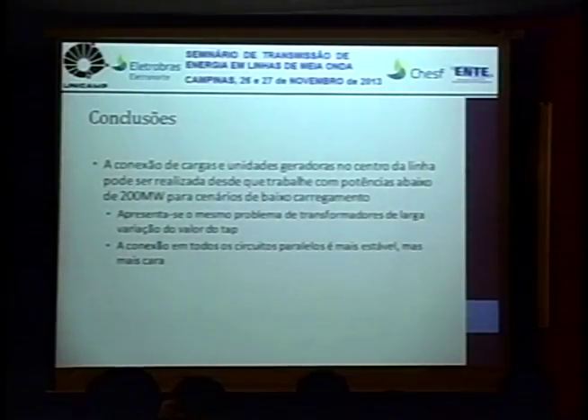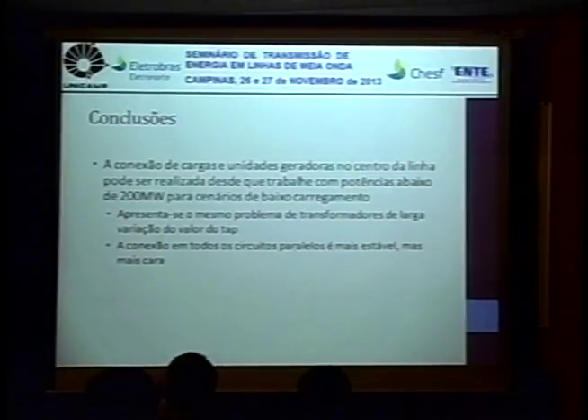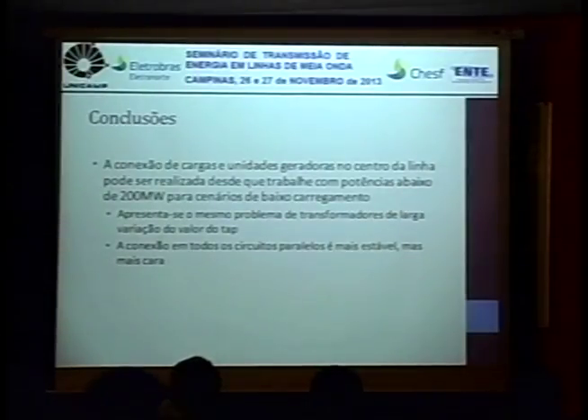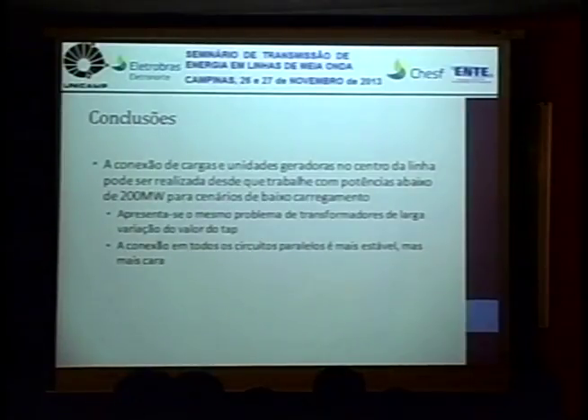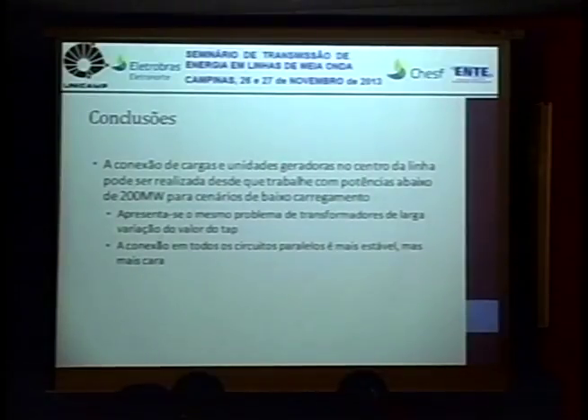More conclusions? The connection of loads or generating units can be done as long as they work with powers up to 200 megawatts. This conclusion is more related with the diverging problems we started to find in the load flow. Another problem we would have with these taps, but one possibility would be to use converters to adjust the voltage, because when there's a variation in the operating voltage in the line, it would demand a voltage control in the transformer working with those intermediate loads. But Antonio Carlos has already talked about the possibility of using converters to do this.